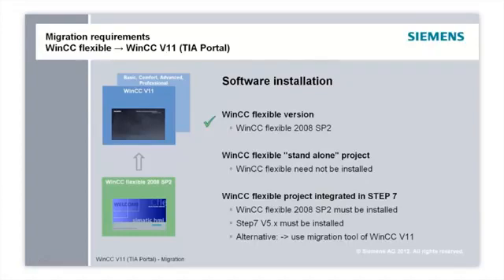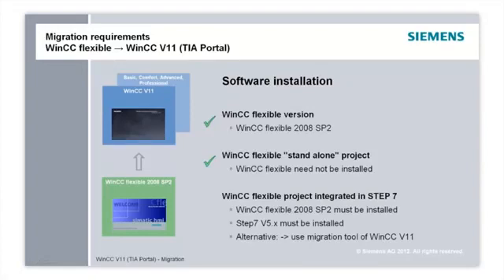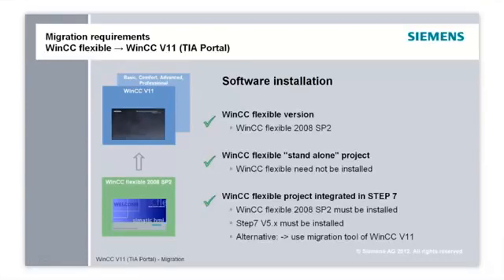When using a standalone project, WinCC Flexible need not be installed on the computer for migrating to WinCC version 11. When using a WinCC Flexible project integrated in Step 7, WinCC Flexible and Step 7 must be additionally installed on the computer. Alternatively, the migration tool can be used, which is available on the installation DVD of WinCC version 11 under Support.